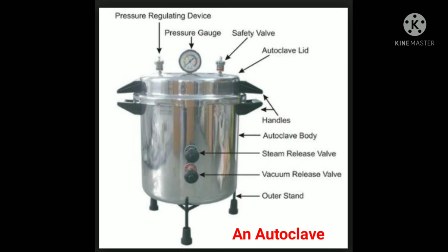At this temperature, saturated steam destroys all vegetative cells and endospores in a small volume of liquid within 10 to 12 minutes. Treatment is continued for at least 15 minutes to provide a margin of safety.